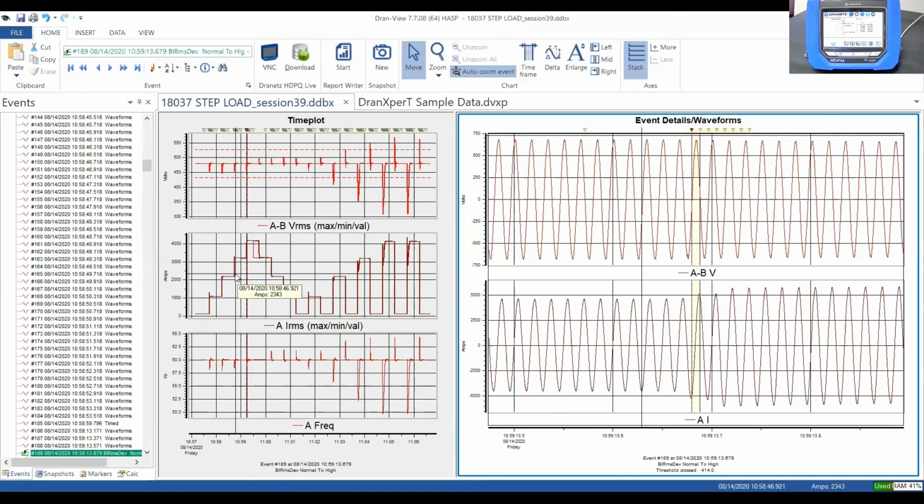Just to review what Ken said, there's just a couple things that you really need to change for this from the standard PQ mode monitoring that's in the instrument. One is the recording depth. Make sure you have the recording depth. We usually suggest 30 pre and X post. And the post, that's for your application. So if you need it to be a minute, you might want to set it a little bit beyond that. So you guarantee you're going to get the pre and the post triggers from that.